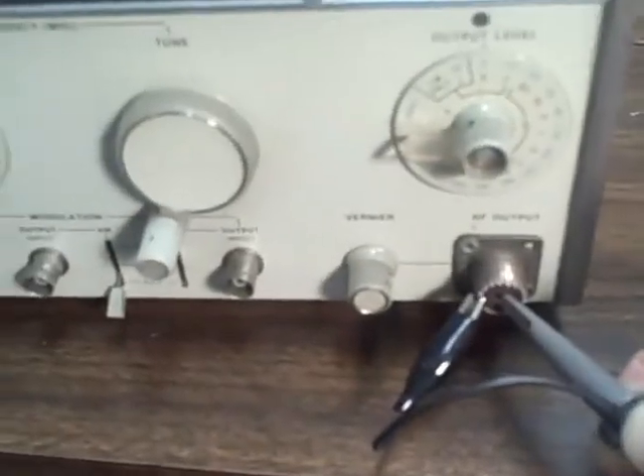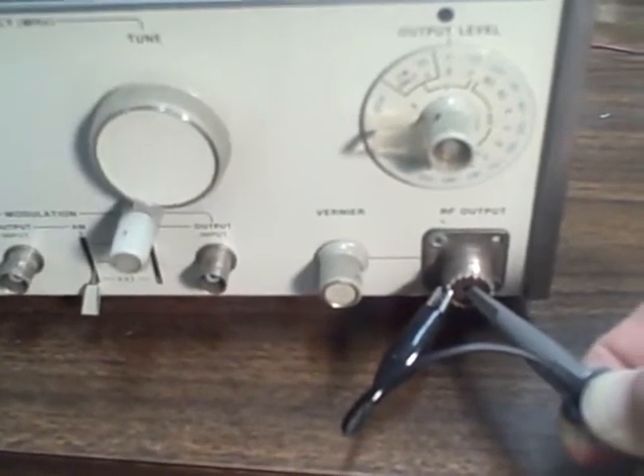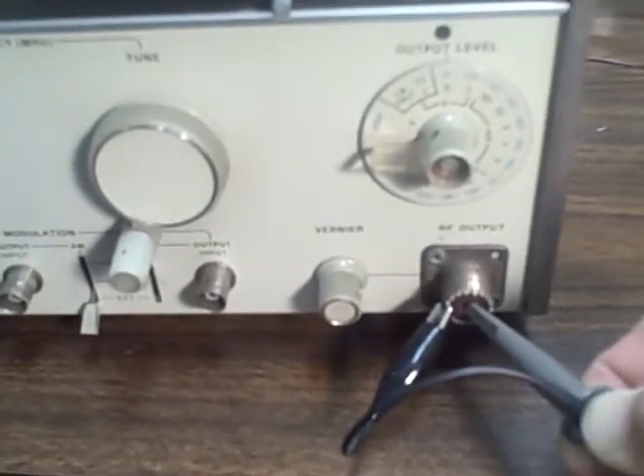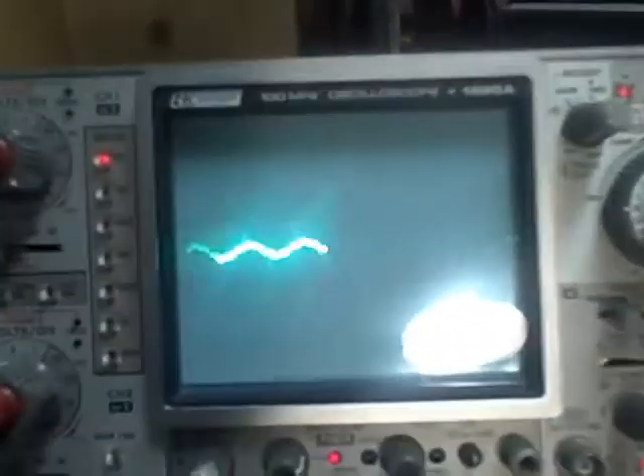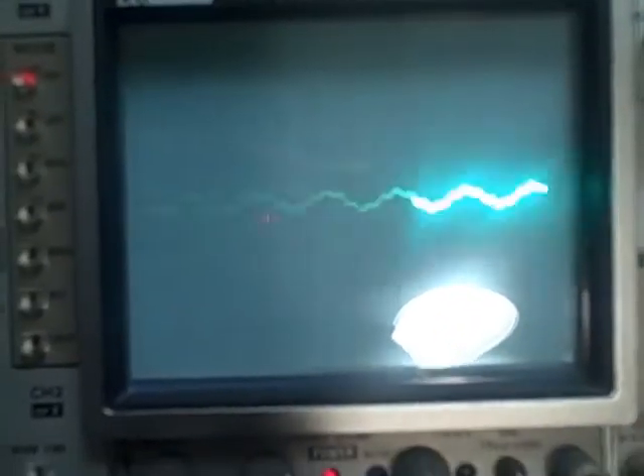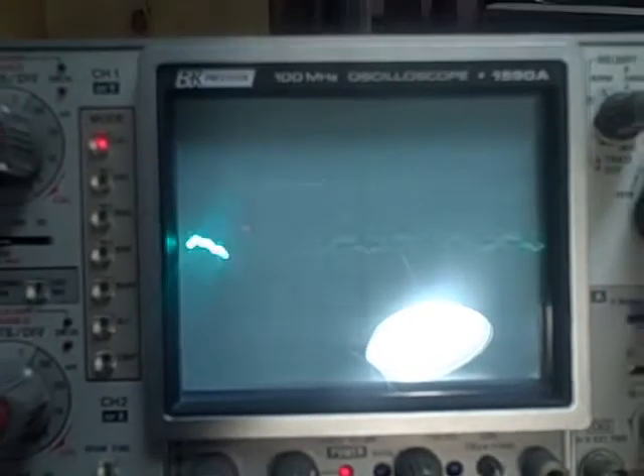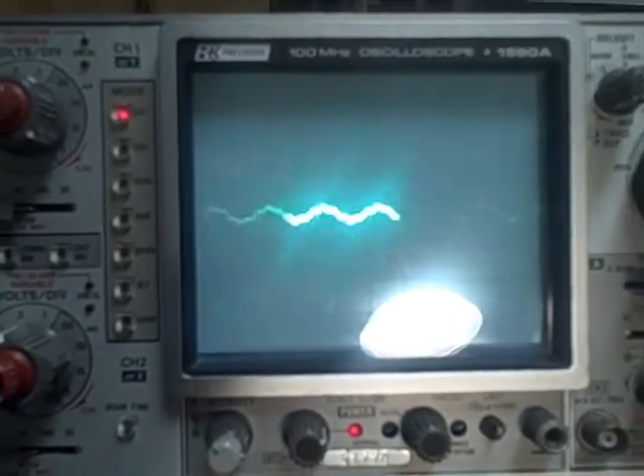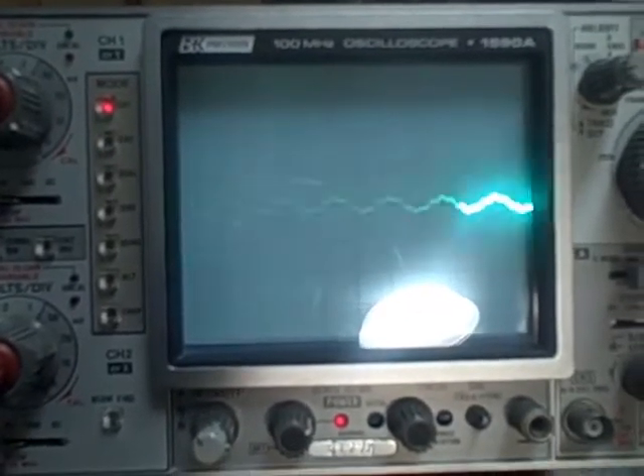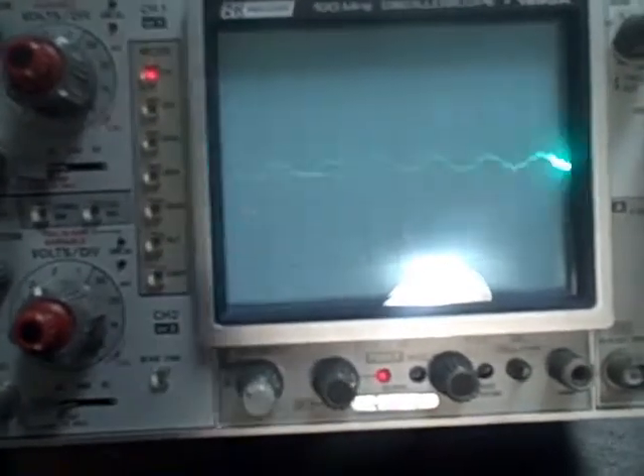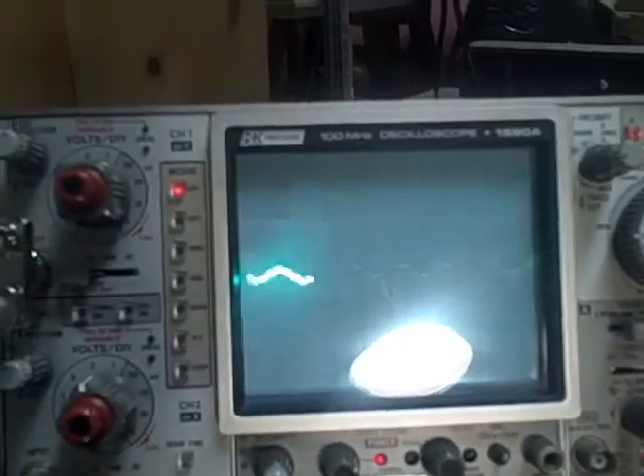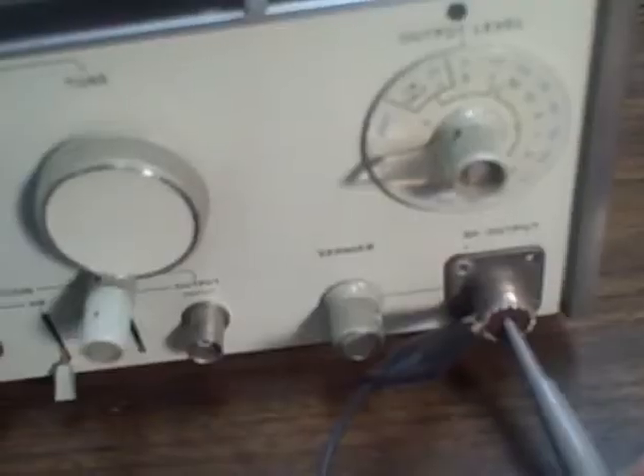Okay, I have the probe inserted, and I'm touching the metal just inside the RF output center terminal, grounded to the case, and the output on my scope shows me that I have a very low amplitude 60 hertz signal, but no RF. I am setting at 5 millivolts per division right now, but I am coming in on the 10 meg side of the probe, so I'll go to the ×1 and see what happens. Alright, there's been no appreciable difference. So I'm getting a 60 hertz signal with some harmonics on it, but I can turn up the scale.